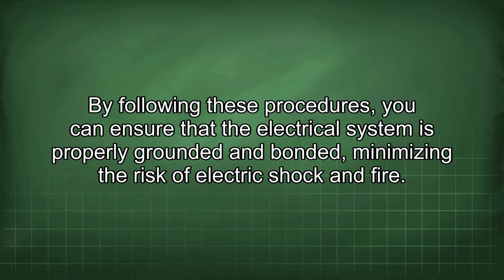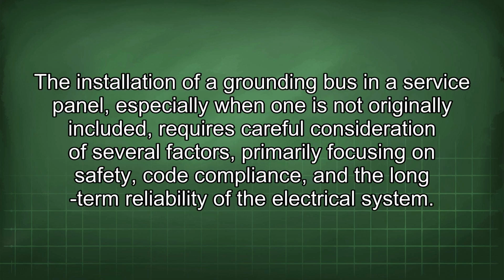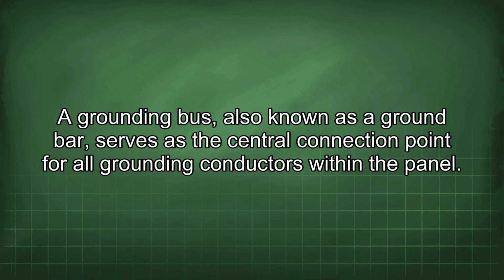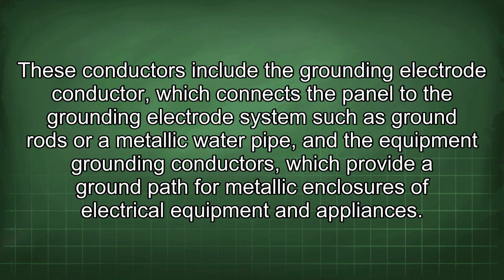The installation of a grounding bus in a service panel, especially when one is not originally included, requires careful consideration of several factors, primarily focusing on safety, code compliance, and the long-term reliability of the electrical system. A grounding bus, also known as a ground bar, serves as the central connection point for all grounding conductors within the panel. These conductors include the grounding electrode conductor, which connects the panel to the grounding electrode system such as ground rods or a metallic water pipe, and the equipment grounding conductors, which provide a ground path for metallic enclosures of electrical equipment and appliances.